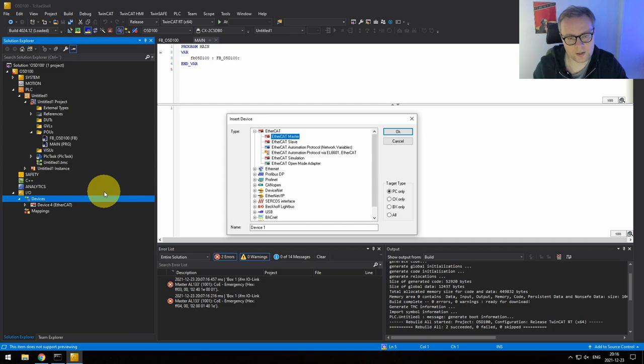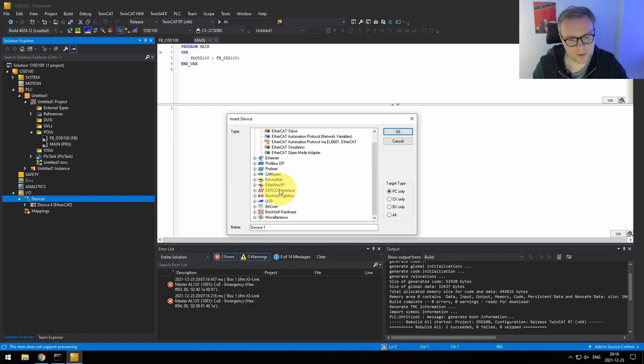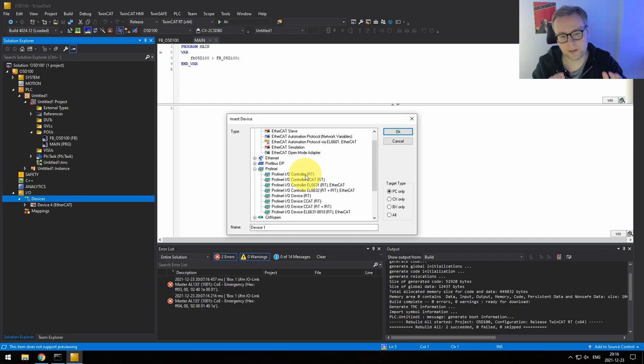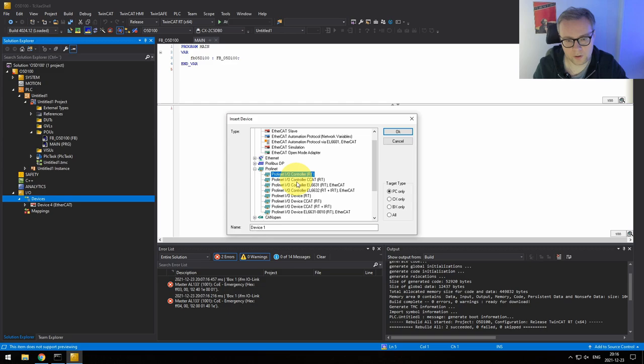One thing worth mentioning: we're running EtherCAT here, but it's very easy to add any other fieldbus protocol. If you right-click, you can see it's not just EtherCAT — you have Profinet, CANopen, DeviceNet, EtherNet/IP, and basically everything. If you want a Profinet driver, for example — Profinet is quite common since its inventor is Siemens, which has a big market share — you can create a Profinet controller. Beckhoff provides real-time drivers for various fieldbuses that you can link to any supported network adapter.